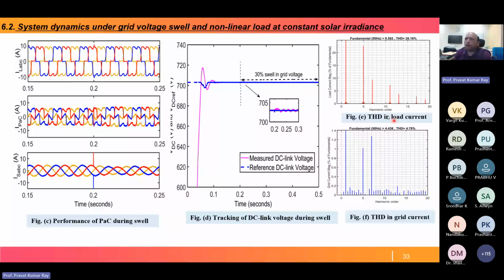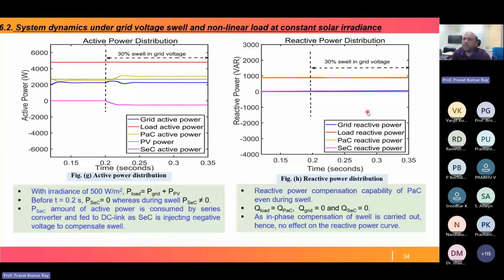Now coming to power distribution, active and reactive. Just like we discussed in the sag case, the swell case is also there, but here active power is consumed instead of provided. That's why the pink color dips below zero, consumed by the series converter and fed to the DC link, as the series converter injects negative voltage to compensate the swell. Swelling is there, so we have to inject negative voltage to get the perfect voltage.